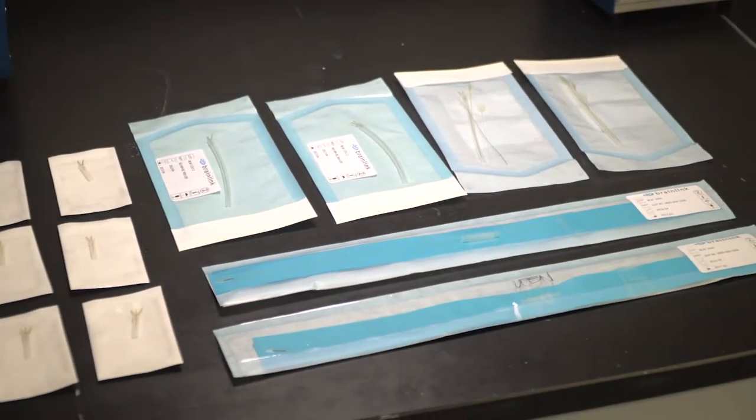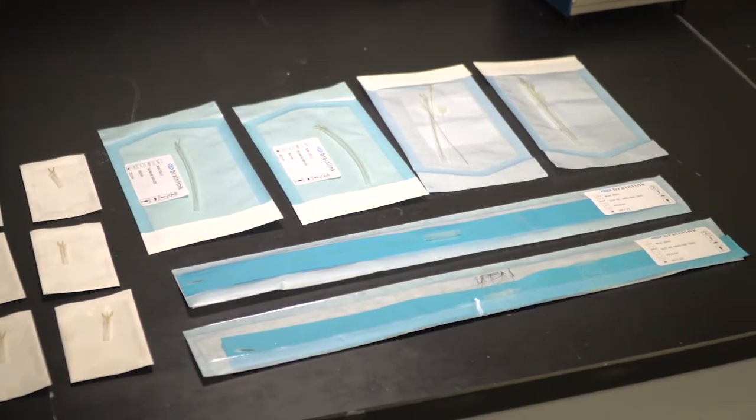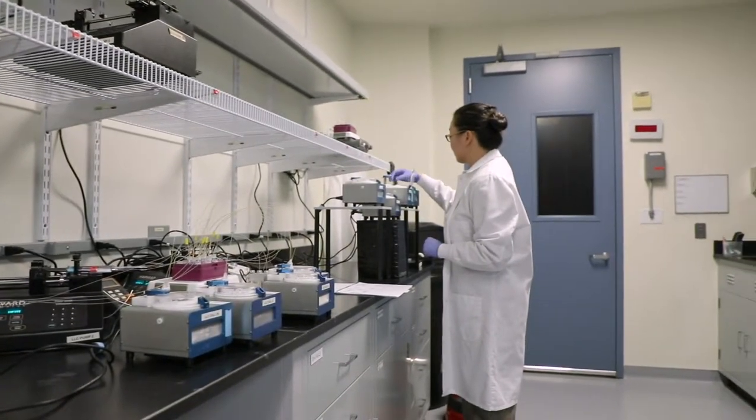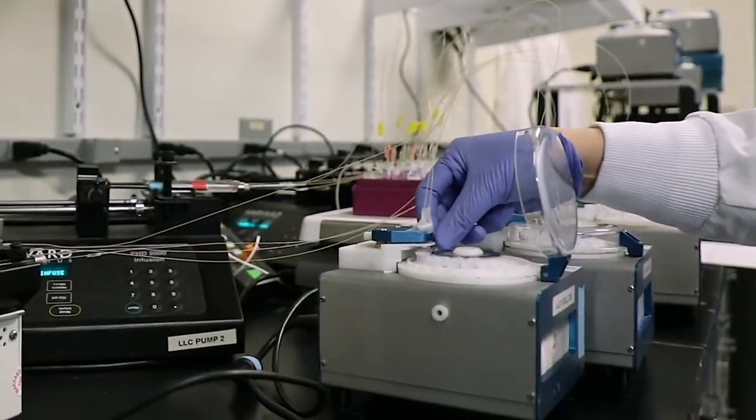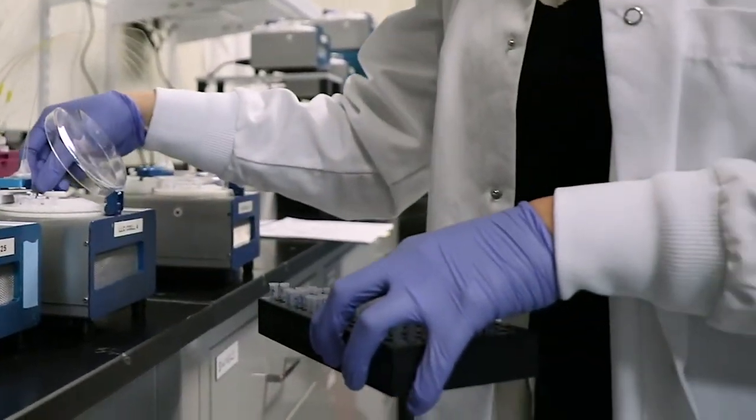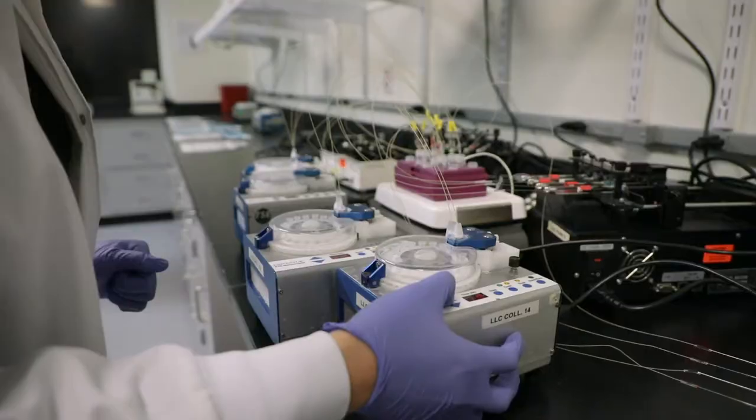The MedaQuant microdialysis probe is a proprietary probe that was developed many years ago to measure quantitative levels of primarily drugs in the brain. This technique allows us to have a very slow flow through the microdialysis probe which allows close to 100% of drug to pass from the outside of the probe in the brain through the membrane, which is then picked up by the carrier flow and diluted at a known concentration.